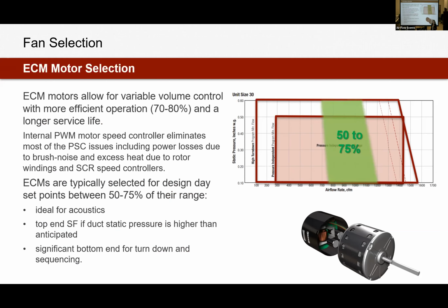And then as far as sizing airflows, we typically recommend keeping your fan size between 50 and, I usually go up to about 80% of its top end range. We don't want to be sizing a fan to operate way out here. It's going to be loud. It's literally screaming. And then you lose any adjustments, you have no more room in the fan. You put a water coil on it, and immediately you're outside of that box. So try to stay within at least 80% of its top end, usually down to 50. We also don't want to be sizing too low. It's a little easier with ECMs. It's okay if you're on the lower end, but you might as well just drop down a box size at that point if you can.